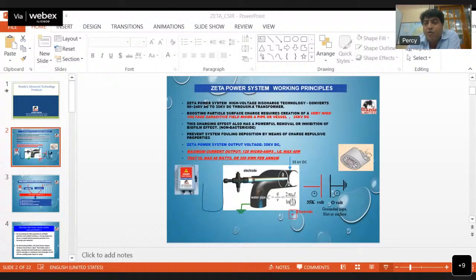So you see, before zeta and after zeta, how clean all the plate heat exchangers or the heat exchanger tube sheets become. This is online, and you don't have to stop your plant at all. It is online and continuous. Now, whenever you have a chiller, if the temperature increases even by 1 degree centigrade, you have a drop in capacity by 10%. So it is very important to have clean and good temperature of cooling water.